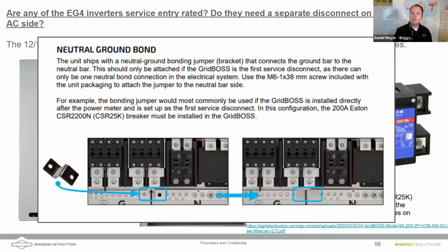If you're going to do that, remember that we only want one neutral ground bonding location in a home, at the place of disconnect. So if you are going to install this breaker, they do include a bonding jumper that allows you to bond the ground and the neutral together inside of that Grid Boss. Make sure you read the manual carefully. I got a little snippet here, but just make sure you understand what you're doing when you're making this a service rated disconnect.